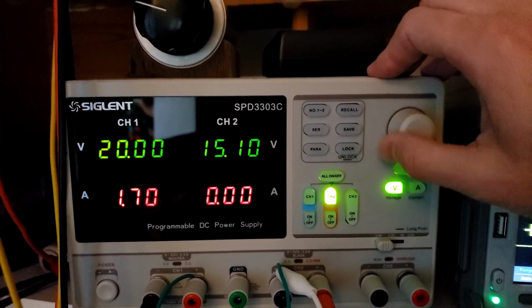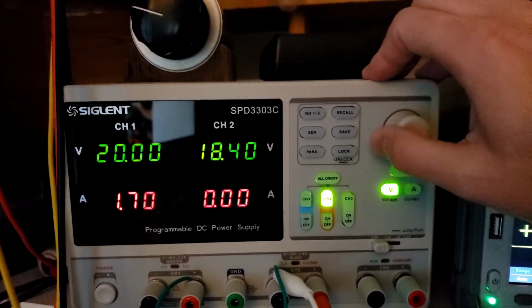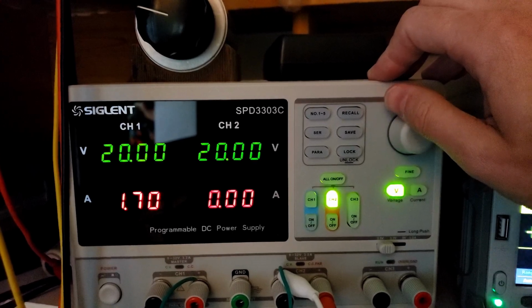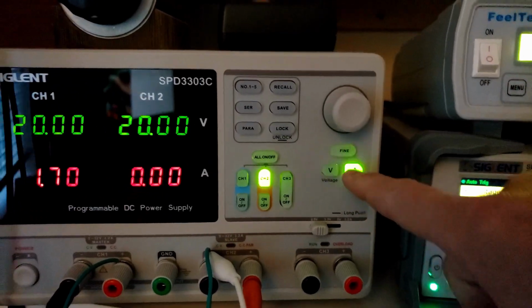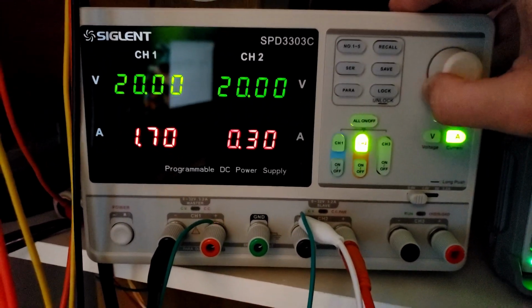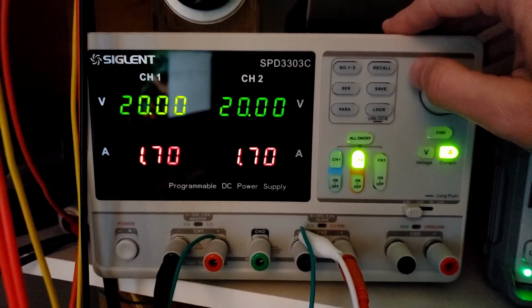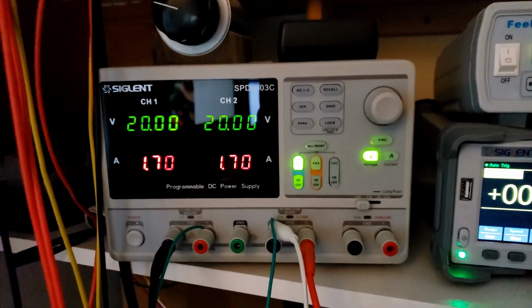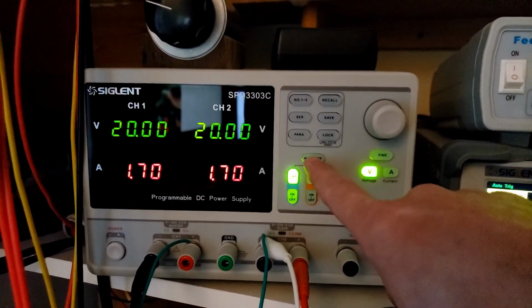Eighteen, nineteen, 20. Then we click amps again to tell it how many amps we want to program, and we push it to 1.7. Go back to channel 1. Now it's set. So now what I've been doing is I'm just pushing all on.